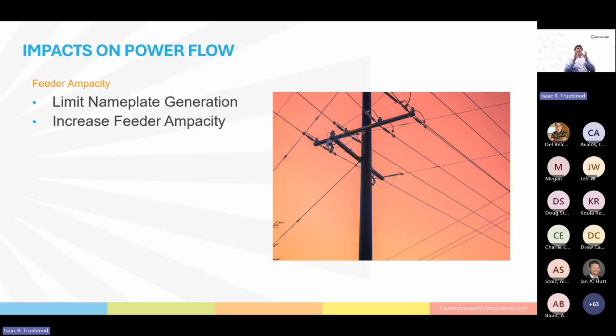However, if there is intended backflow, the distributed energy resource's generation minus that downstream load may still exceed a feeder's ampacity, and the ampacity of the line and or equipment between the substation and that feeder, and between that substation feeder and that distributed energy resource. When I say the ampacity of the feeder, it means all parts of the feeder. This will generally require a review of everything on that feeder the distributed energy resource may exceed the ampacity of. This includes lines, switches, breakers, connection or jumper connections, fuses, relays, relay settings. It is a non-insignificant review.